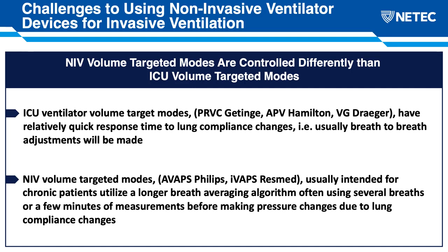Whereas the non-invasive devices, oftentimes, because they're made for more of a chronic patient and they are looking at a lot of leaks when you're utilizing a mask, but here if we're using it invasively, just remember that those algorithms are a bit slower. Oftentimes they're looking at either a minute or a couple of minutes to average, or a several breath average in their algorithm before they start making pressure changes to make sure that you're getting the delivered volume.